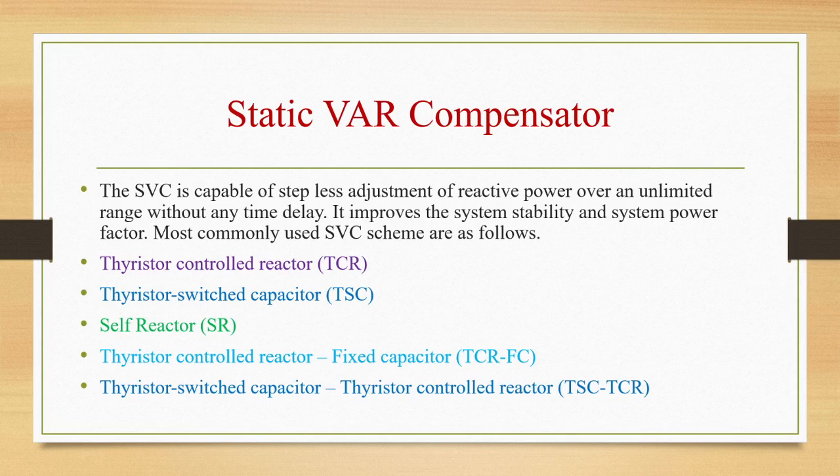SVC, static VAR compensator, is capable of stepless adjustment of reactive power over an unlimited range without any time delay. It will improve the system stability and system power factor. So, following are the most commonly used SVC schemes. First one is thyristor controlled reactor, that is TCR. Second one is thyristor switched capacitor, TSC. Third is self reactor, SR.